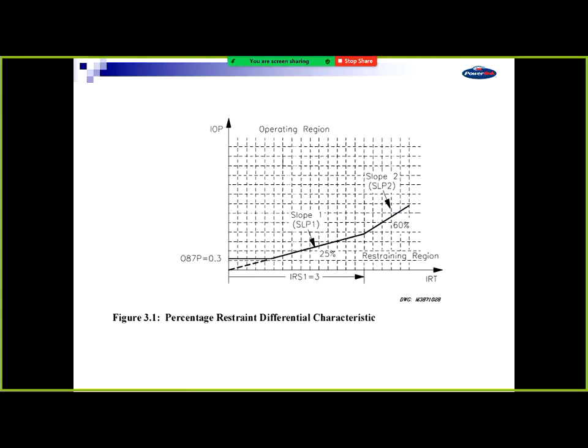That's just another drawing of how that can be shown. The 87P stands for a differential operation. So it's the same thing, 2 slopes, a pickup of 0.3, a slope of 25%, a slope of 60%. That looks like it's come out of a relay manufacturer manual. That's what we would use. We do our calculations and compare them to this. If we say we need more, we'll make it more. If we say we don't need that much, we'll use their settings. They've got feedback from wherever they're selling these relays, and they say our relay is stable and works correctly with these settings. So that's why we use them as a default, but we check by doing calculations ourselves.